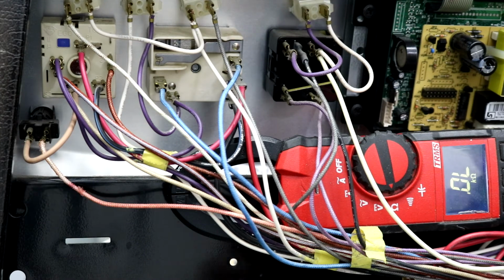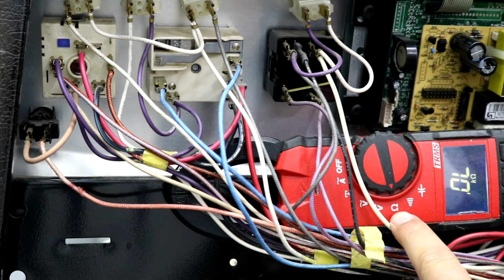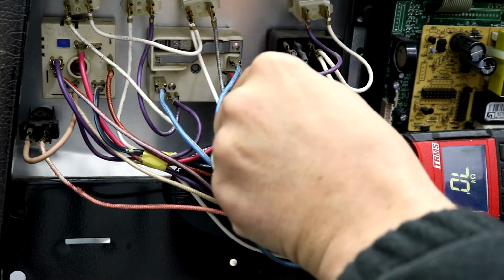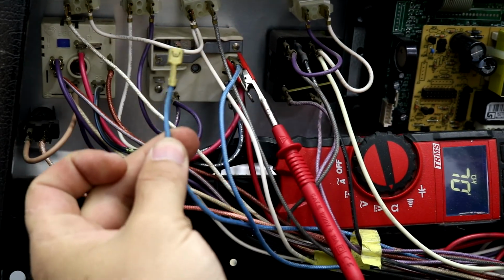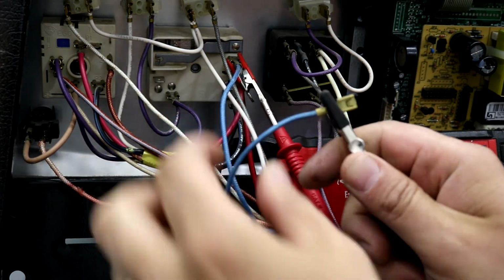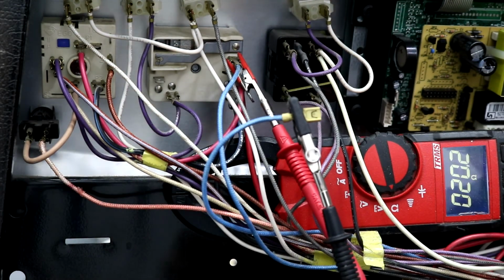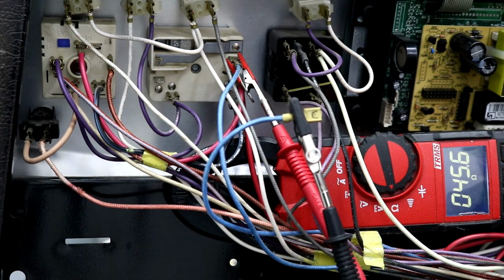Okay, so to test this burner and switch, if you have a burner that's not working, it's pretty simple. We can use the process of elimination. We'll set our meter to ohms, and we'll connect on one of the wires that goes to the burner, and then we'll remove the other one from the switch and attach onto that. And you should get a resistance reading of about 45 ohms. That means the contact on the high temperature probe is closed and the burner windings are good.